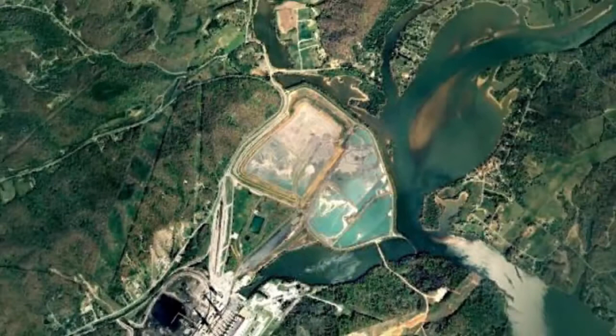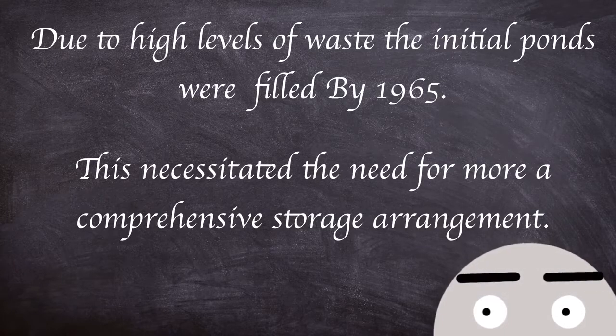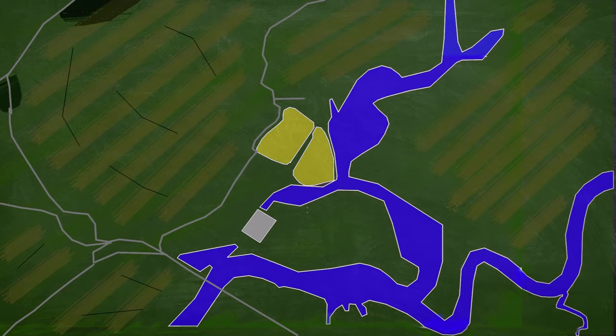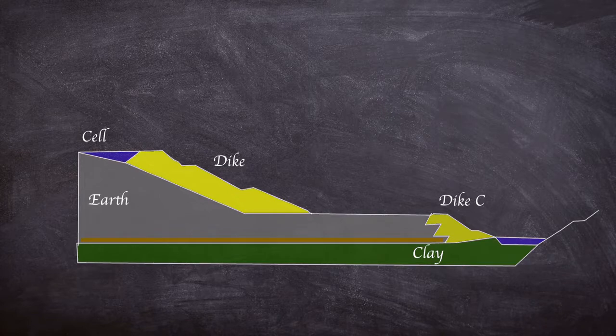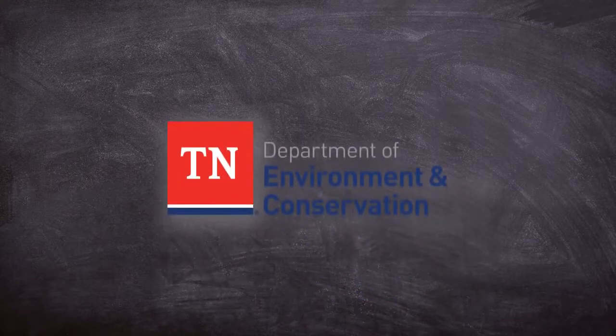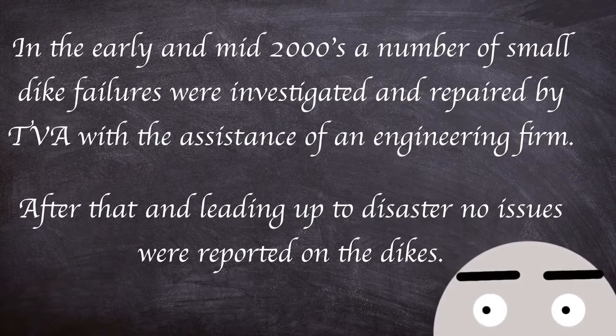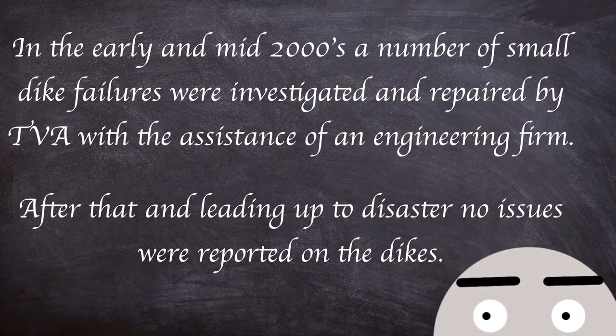Since commencement of operations in the 1950s, the plant had been storing its coal ash in containment ponds adjacent to the Emory River. Due to high levels of waste, the initial ponds were filled by 1965, necessitating a more comprehensive storage arrangement. A new settling pond and ash storage cells were constructed, divided into a number of smaller dredge cells with a perimeter 60 feet above winter level and 740 feet above sea level. Dikes were stacked on top of each other over previously sluiced ash materials. These dikes were visually inspected daily by workers, with more in-depth surveys undertaken by engineers yearly and quarterly checks by the Tennessee Department of Environment and Conservation. In the early to mid 2000s, a number of small dike failures were investigated and repaired by TVA with the assistance of an engineering firm, after which no other issues were reported on the dikes.